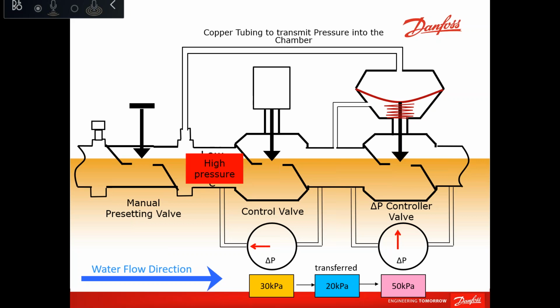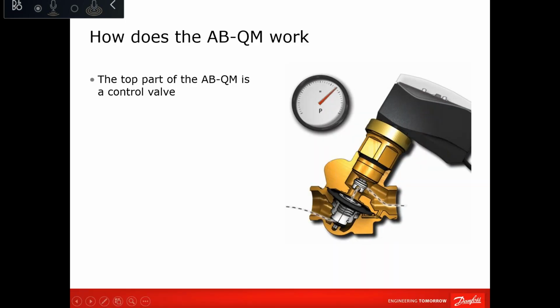For sizes up to DN32, the differential pressure part comes first, and then the control valve comes second. For DN40 up to DN250, the control valve comes first, like the drawing I'm showing here, and then the differential pressure controller comes after. Why is that? It's simply because up to DN32, it's a compact one. As you can see in this graph, the pressure of the water is pushing the disc and membrane to close, while on the small size, the system pressure is pulling the membrane to close. One is push, one is pull.